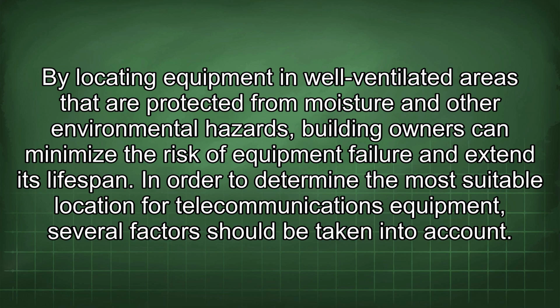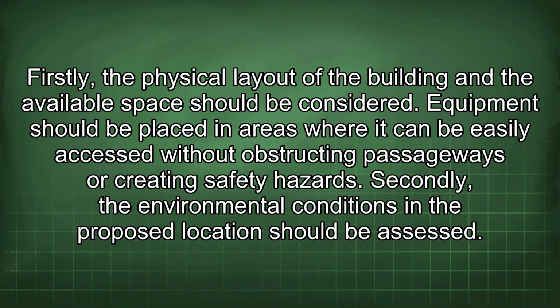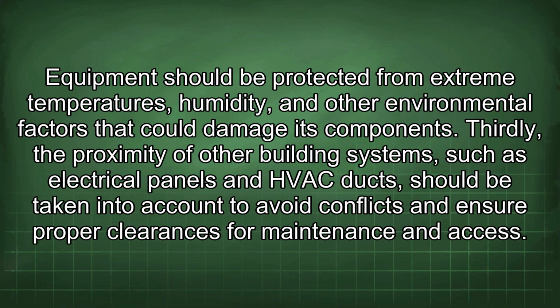In order to determine the most suitable location for telecommunications equipment, several factors should be taken into account. Firstly, the physical layout of the building and the available space should be considered. Equipment should be placed in areas where it can be easily accessed without obstructing passageways or creating safety hazards. Secondly, the environmental conditions in the proposed location should be assessed. Equipment should be protected from extreme temperatures, humidity, and other environmental factors that could damage its components. Thirdly, the proximity of other building systems, such as electrical panels and HVAC ducts, should be taken into account to avoid conflicts and ensure proper clearances for maintenance and access.